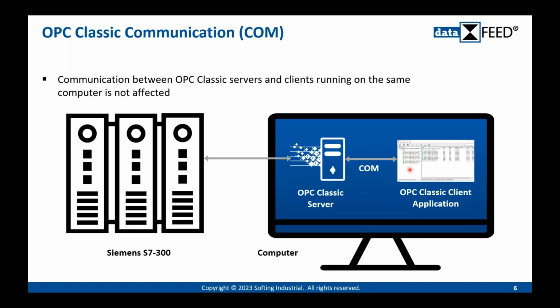Microsoft proprietary COM interface, which means the OPC Classic server and the client can still communicate because the COM interface is not affected by the Microsoft security updates, only the DCOM. That's why, if on your side runs the OPC Classic server and the Classic client application on the same PC, there's no need to do any changes.